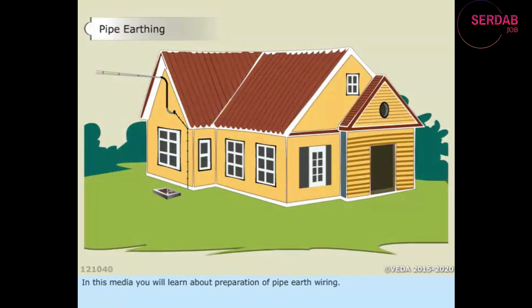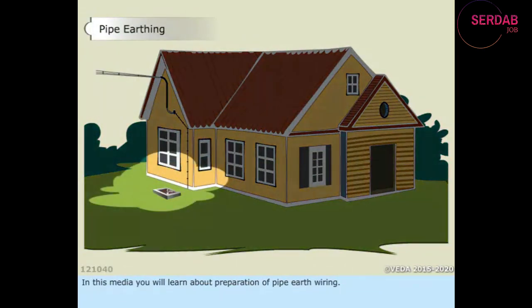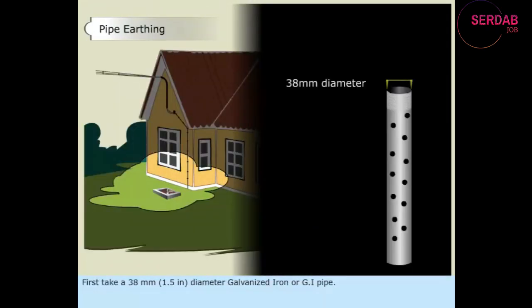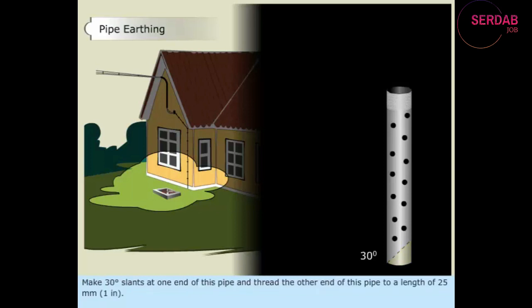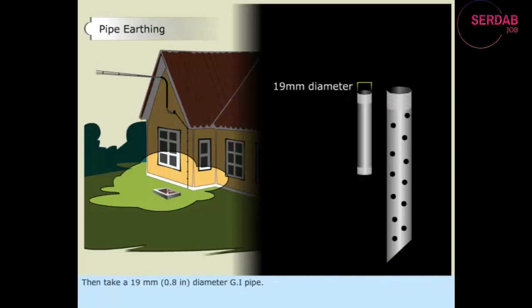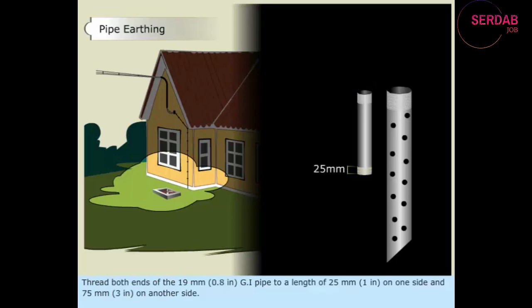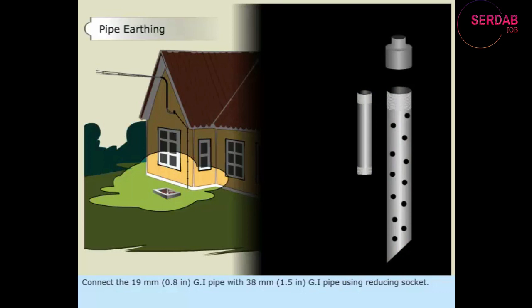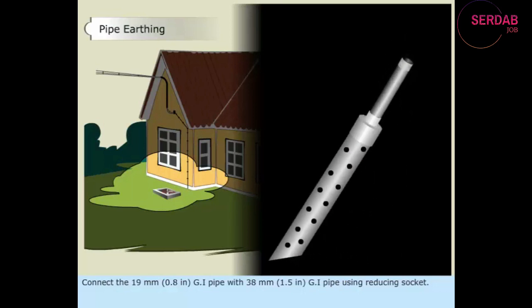In this media, you will learn about preparation of pipe earth wiring. First, take a 38 mm or 1.5 inch diameter galvanized iron or GI pipe. Make 30-degree slants at one end of this pipe and thread the other end of this pipe to a length of 25 mm or 1 inch. Then, take a 19 mm or 0.8 inch diameter GI pipe. Thread both ends of the 19 mm, 0.8 inch GI pipe to a length of 25 mm, 1 inch on one side, and 75 mm, 3 inches on another side. Connect the 19 mm, 0.8 inch GI pipe with 38 mm, 1.5 inch GI pipe using reducing socket.